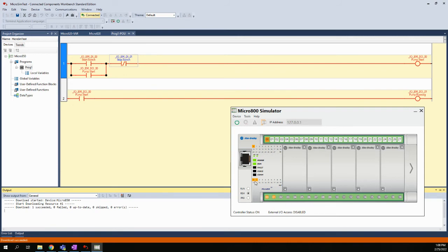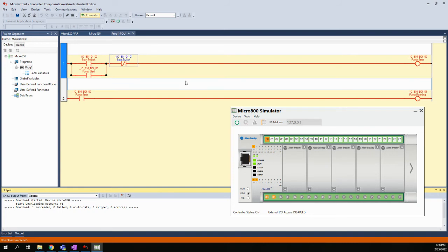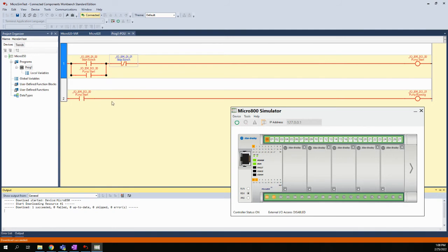Up in the logic, you can see everything turned red. The start switch is on, the pump start contact is on because the relay here is picked up, and then the same contact is used here in this rung and it is also turning on the pump running.